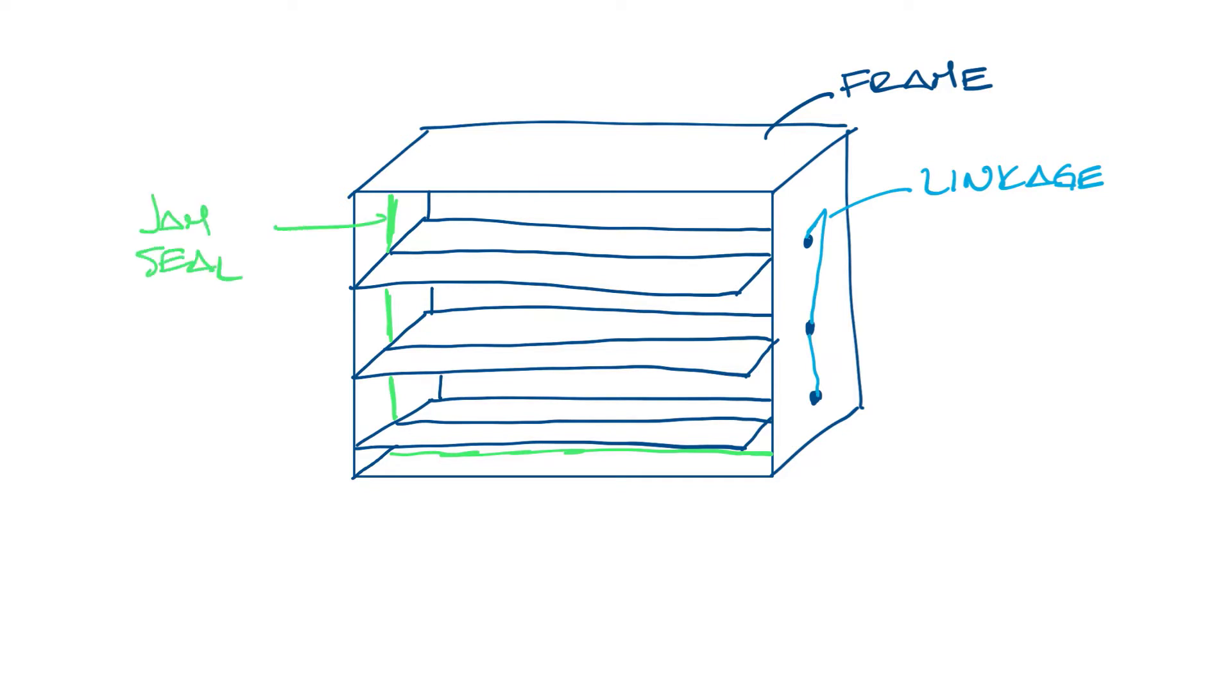So we'll start with the frame of the damper and draw in some blades. So label the frame, and over here you have the linkage that links the blades together so that a single operator can move all the blades at once. There's a jam seal to prevent leakage between the frame and the blades and a blade seal to seal the blades when they're fully closed.